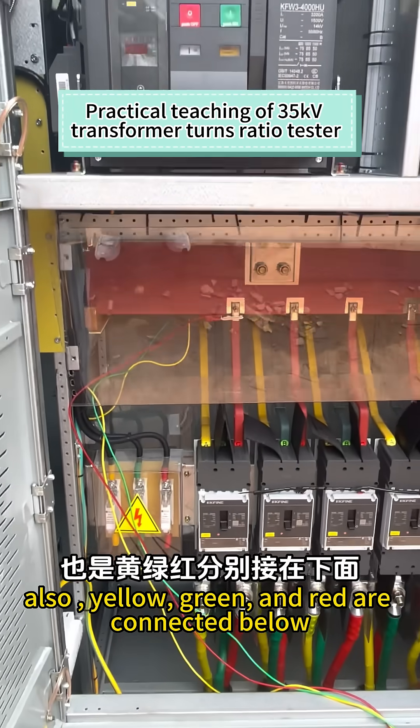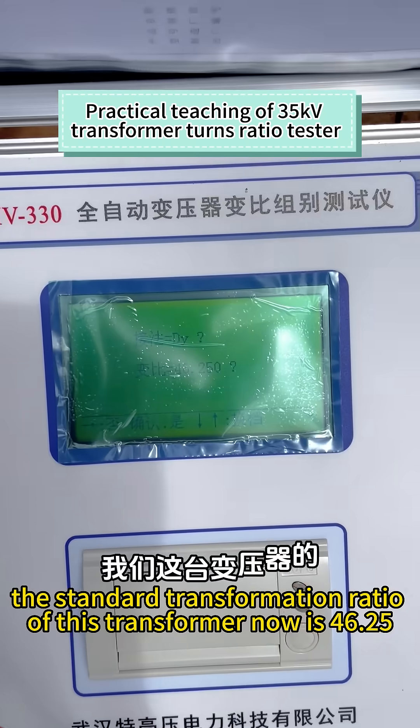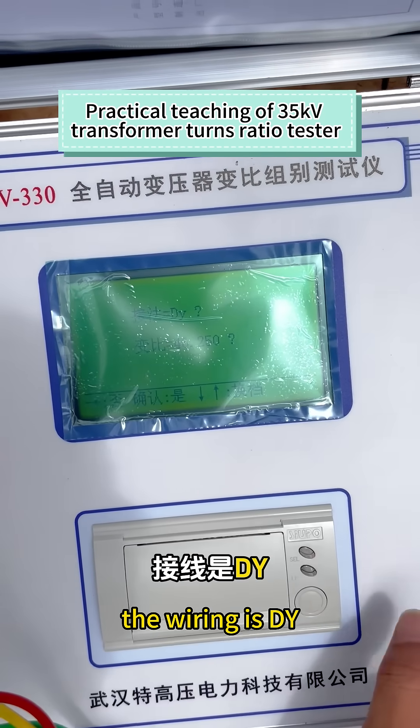Also, yellow, green and red are connected below. The standard transformation ratio of this transformer is 46.25. The wiring is DY. After we set it up, click OK — it starts measuring.